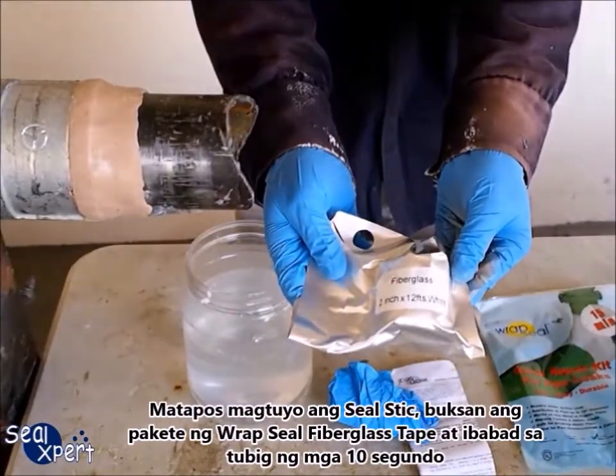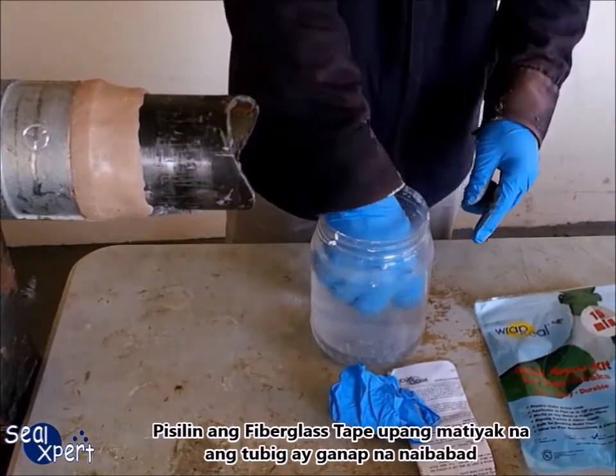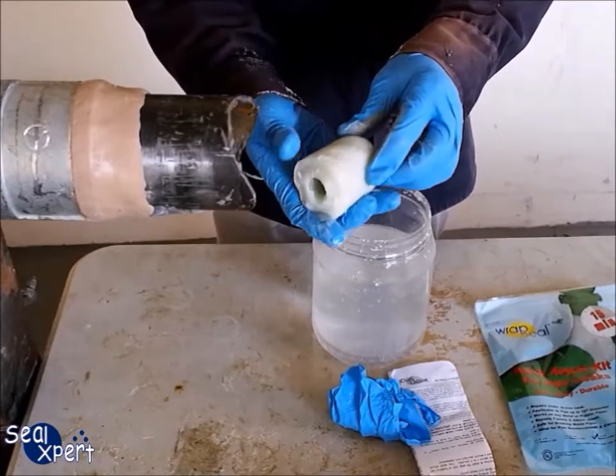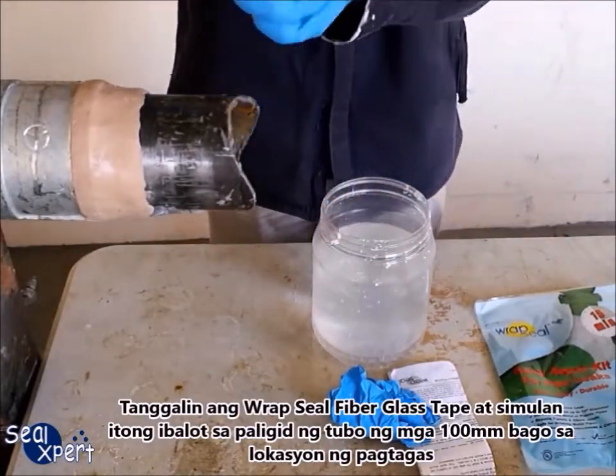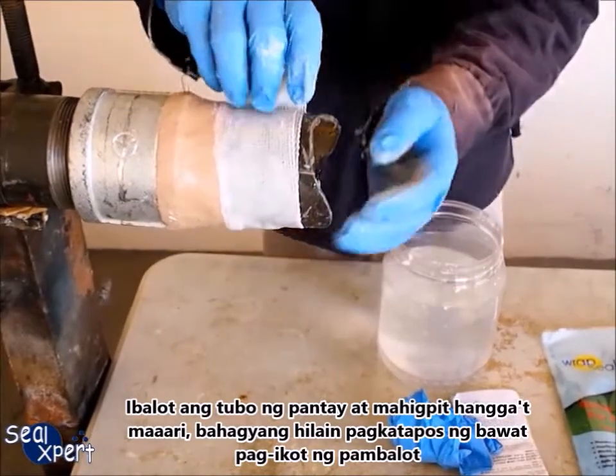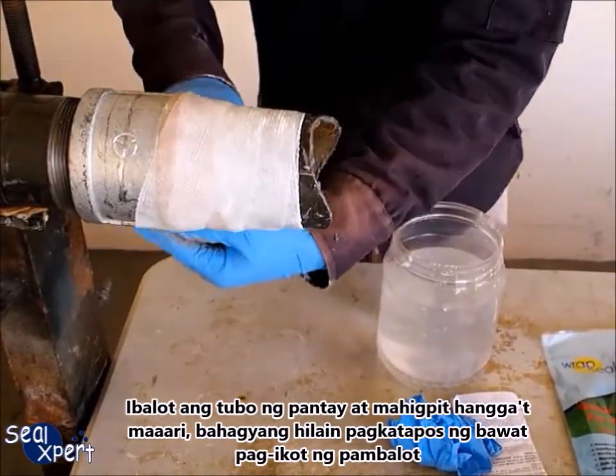After the Seal Stic is cured, open the pack of Wrap Seal fiberglass tape and soak in water for about 10 seconds, squeezing the fiberglass tape to ensure water is fully immersed. Remove the Wrap Seal fiberglass tape and start wrapping around the pipe at about 100 millimeters before the leak location. Wrap the pipe as evenly and tightly as possible, pulling slightly after each round of wrapping.